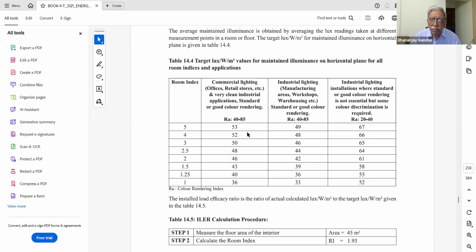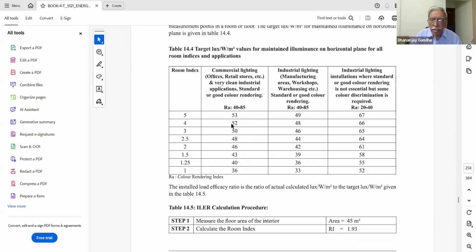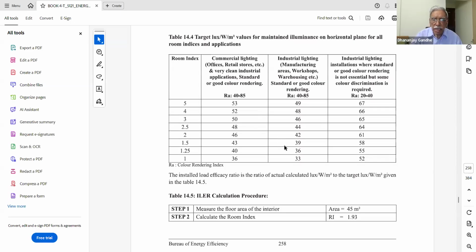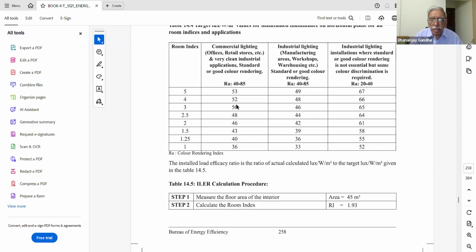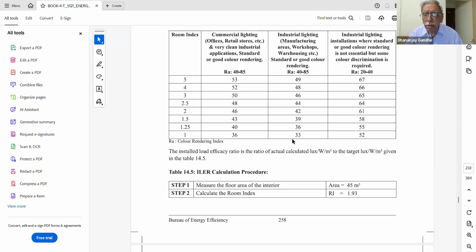So you can see that for different room indices, figures are mentioned for commercial lighting and industrial lighting. For the normal lighting, industrial lighting, on a large scale, these values are set lower, whereas for some standard installations it is higher. These figures are provided as the target lux level, and actual measurements are done physically at that particular place. After knowing the room index for that place, you can see what standard should have been provided and what actual lux level you have measured. This ratio of the two will give you the ILER.